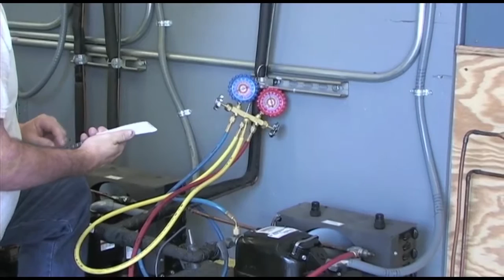34 minus a negative 10, which will give us 44 degrees of superheat. So this system is now operating with 44 degrees of superheat. You will learn as you progress through this program by taking superheat readings and learning pressure characteristics of the system. You'll be able to diagnose refrigeration problems in all of your commercial refrigeration systems.